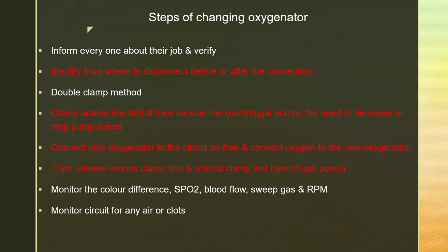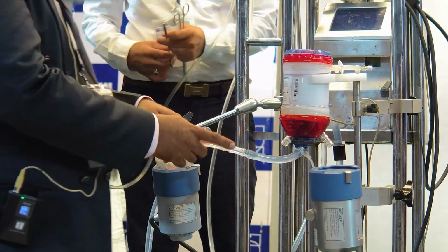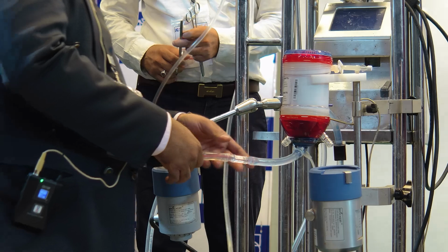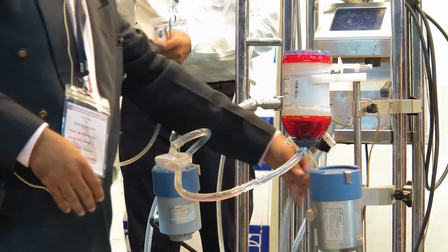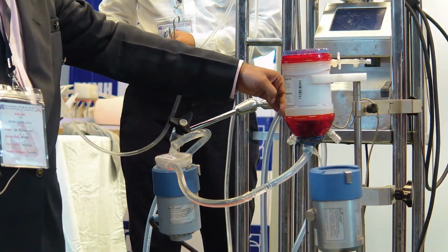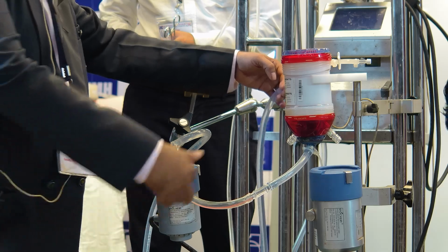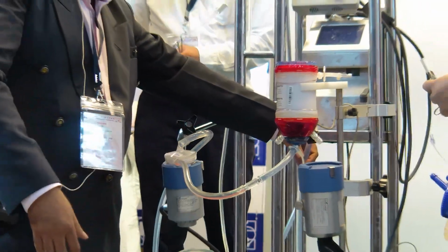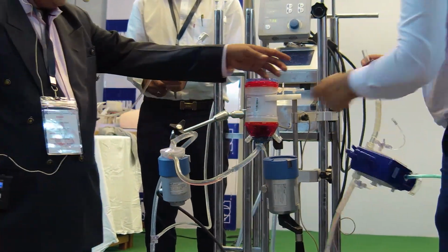So you want to change this oxygenator. You don't require to come down on flow. Just put the clamp - you are going to remove it from here. This is pre-oxygenator, this is post-oxygenator, so put the clamp here. Two places you put the clamp. You cut the tube in between the clamps and then connect again.